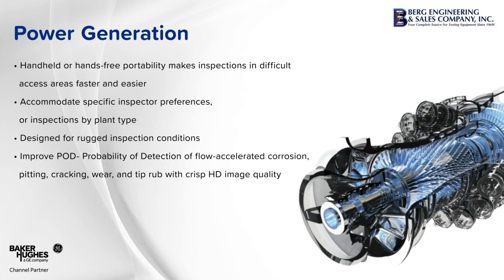And once they're inspecting and are looking for flow accelerated corrosion or pitting or cracking or wear, or on rotating machinery, they may be looking for turbine tip rubs, they'll need the bright HD imaging capability that the Mentor Visual actually provides. And then with the probability of detection package, you turn on things like distortion correction or high dynamic image ranging to allow for better analysis and measuring.